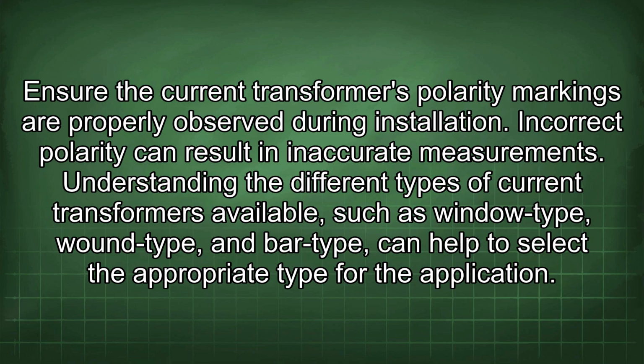Ensure the current transformer's polarity markings are properly observed during installation. Incorrect polarity can result in inaccurate measurements. Understanding the different types of current transformers available, such as window type, wound type, and bar type, can help to select the appropriate type for the application.